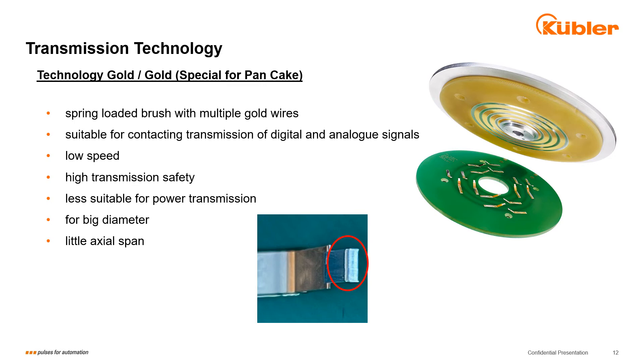For our so-called pancake slip rings, we use a completely different technology. These slip rings build their transmission lines not axially but radially, like the rings of Saturn. The axial span is quite narrow and these slip rings are very well qualified for dynamic systems where the whole slip ring itself is spinning. Typical applications are grippers on pick-and-place machines or arm-end tools in robotics. The brush is a banded spring-type metal strip with an arrangement of fine gold wires at its touching end. The technology is perfectly suited to signal transmission and with certain precautions, fieldbuses work perfectly.